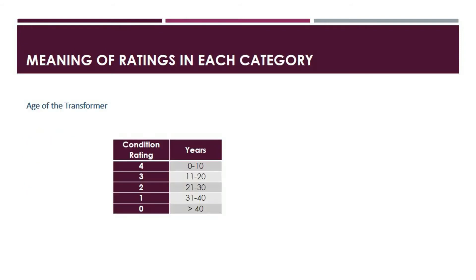Now let us go over the rating categories that compose the health index. First, let us look at the transformer's age. A transformer is assigned a rating of 4 if it is less than 10 years; a rating of 3 if it is between 11 to 20 years; a rating of 2 if it is 21 to 30 years; a rating of 1 if it is between 31 to 40 years; and a rating of 0 for any transformer that is over 40 years of age.